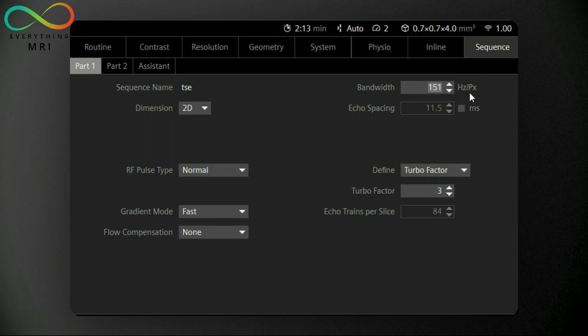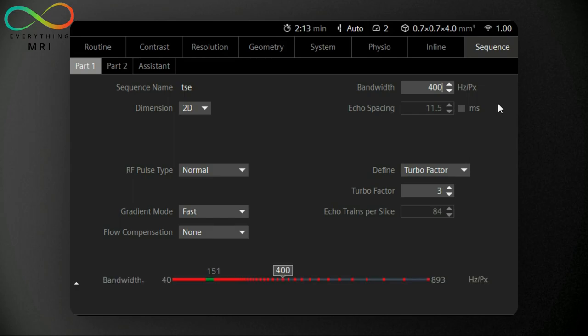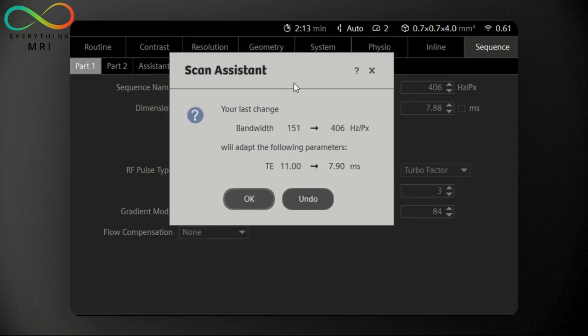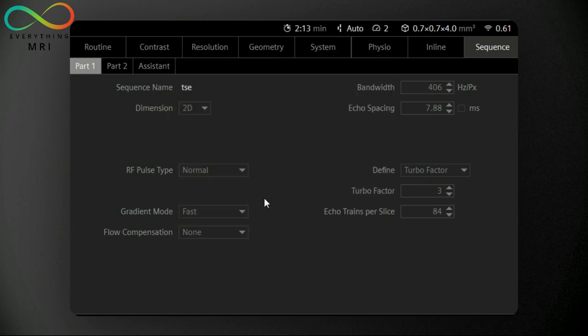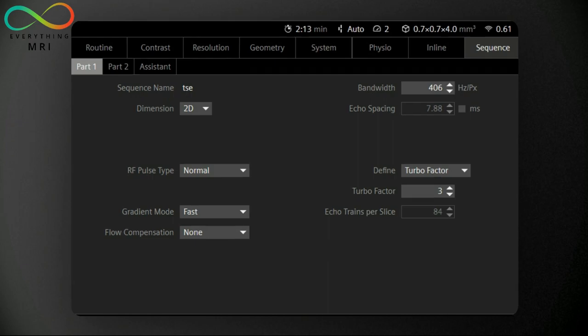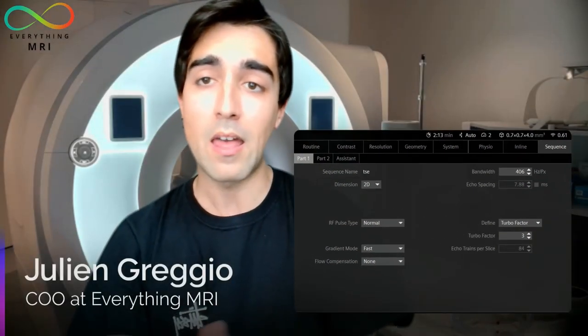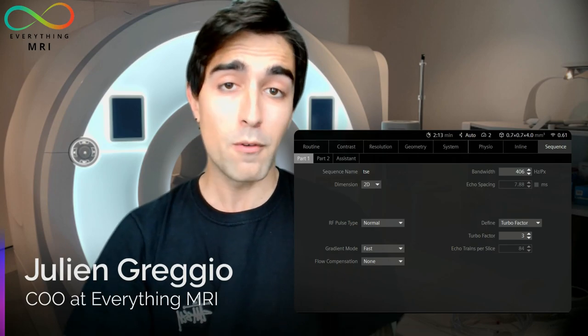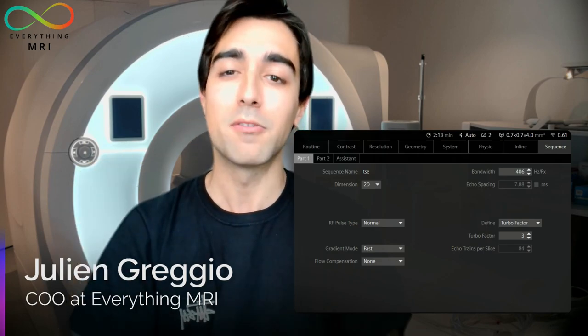You might ask why. The reason is that doubling or even tripling the bandwidth — for instance to a threshold between 400 and 800 Hz per pixel — would have a massive impact on reducing the number of in-plane distortions on our images. We went through the differences between in-plane and through-plane distortion in our previous video; if you missed it, just click on the link in the description.